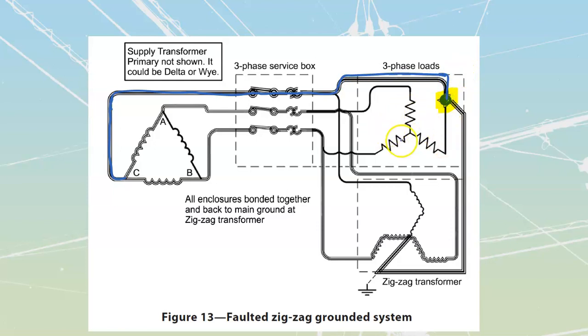Now some of it could go back to the loads. There will still be a little bit, but the bulk of it is now going to be able to divert. It's looking for the path of least resistance. The bulk of it's going to divert onto the bonding pathway, travel along the bonding pathway, and come back up that, and hit the neutral of my zigzag transformer.